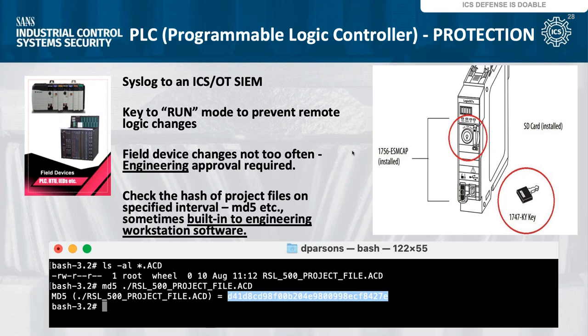In general, we have seen with the TRISIS malware, for example, exactly that - changes of the ladder logic code remotely over the network. In some cases, not specifically with Trisys, using that key and putting the PLC in run mode will prevent remote access to it. And yes, that means you'd have to physically go there to change the PLC.